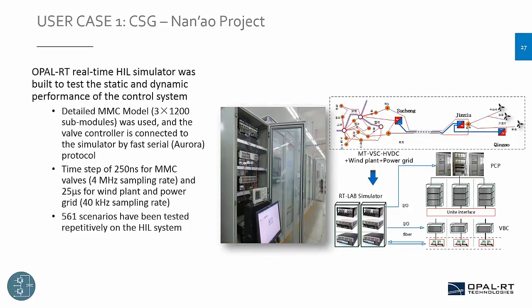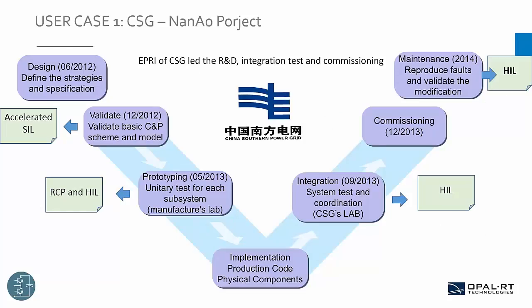The time step of the MMC valve was 250 nanoseconds, or the sampling rate was 4 megahertz, which is very fast. And we used 25 microseconds to simulate the wind plant and the power grid around the MMC HVDC system. There were 561 scenarios that have been tested repetitively on the HIL system. So at the end of the V cycle, the HIL model has been fully validated at all the different stages.